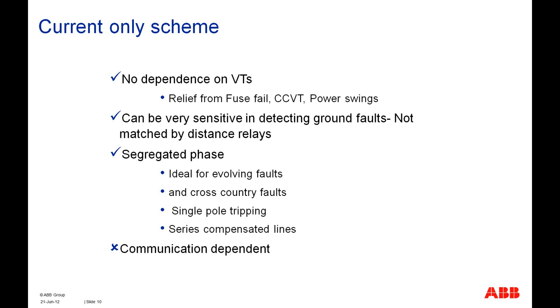The only disadvantage of the line differential protection scheme is the communication part of it. If we lose communication for some reason, then we will lose the line differential protection, and we'll have to fall back on other types of protection like distance protection, or maybe in some cases just the overcurrent or feeder protection only. But with the advancement we are making in communication technology, line differential protection is becoming more and more popular as compared to, for example, distance protection.